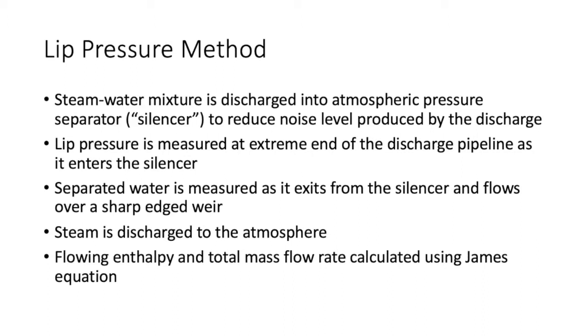To apply the lip pressure method, the steam-water mixture is discharged into an atmospheric pressure separator — also called a silencer — that reduces the noise level produced by the discharge. The lip pressure is then measured at the end of the discharge pipeline as it enters the silencer, and the separated water flow exiting the silencer is measured over a sharp-edged weir while steam is discharged into the atmosphere. Flowing enthalpy and total mass flow rate are then calculated using the James equation.